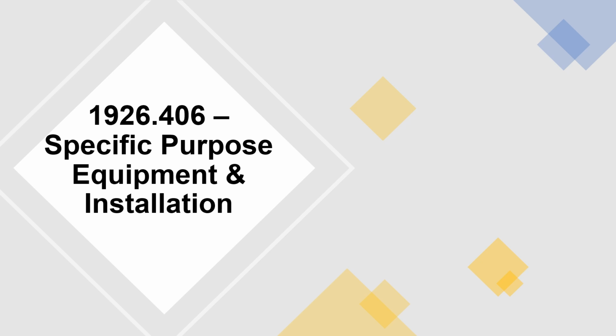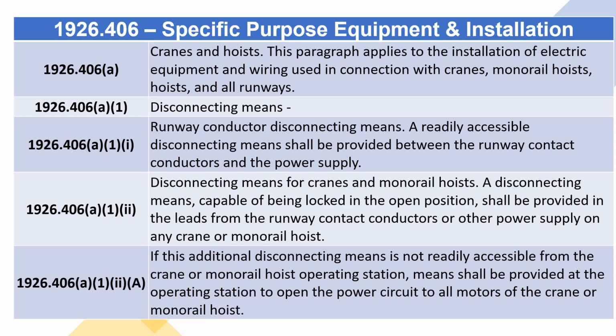1926.406 Specific Purpose Equipment and Installation. 1926.406(a) Cranes and hoists. This paragraph applies to the installation of electric equipment and wiring used in connection with cranes, monorail hoists, and all runways. 1926.406(a)(1) Disconnecting means. Runway conductor disconnecting means. A readily accessible disconnecting means shall be provided between the runway contact conductors and the power supply.